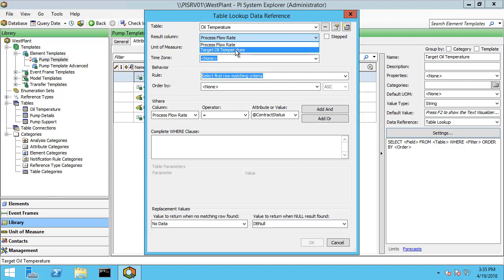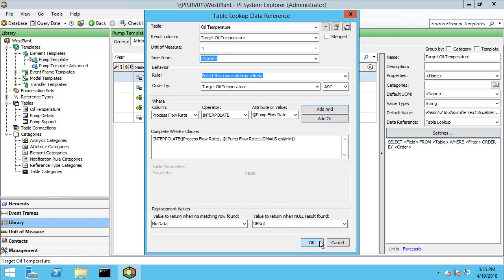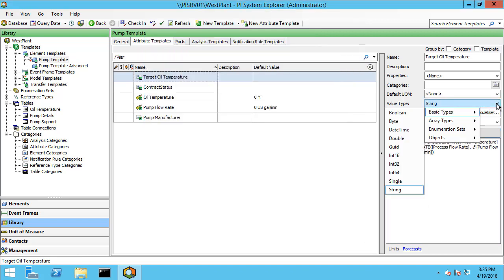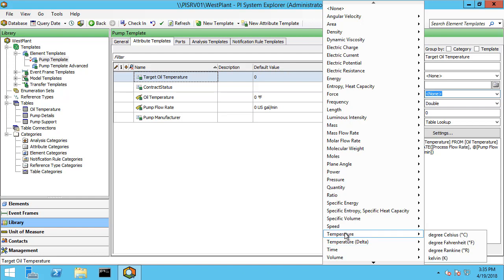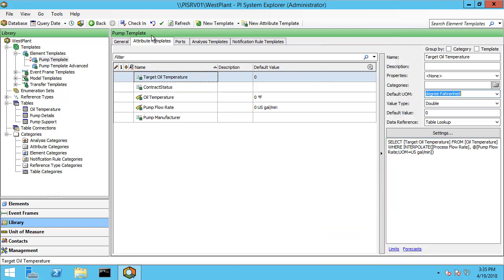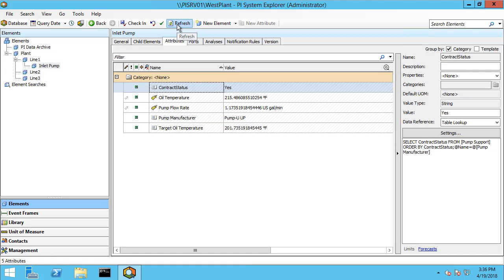Our data reference type will be a table lookup, and under settings let me pick the correct table. The resulting column will be the target oil temperature. Our WHERE clause is related to the process flow rate and we need to interpolate, and the attribute that stores that information is the pump flow rate. Go ahead and click OK — this is actually going to be a value so let me change the type to double, and our default unit of measure will be Fahrenheit to display it. Let me check that in. Under elements, hit refresh, and now with a current flow rate of 1.17, our target oil temperature based on interpolation from that table is 201.7.